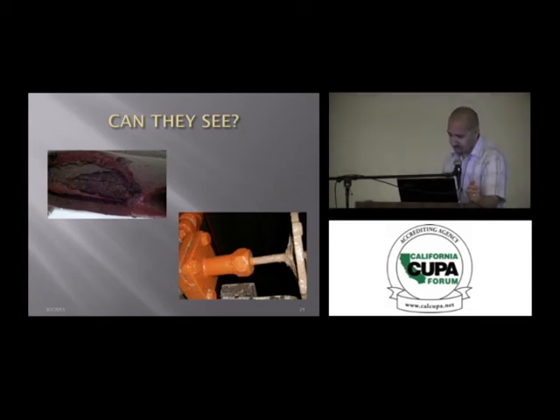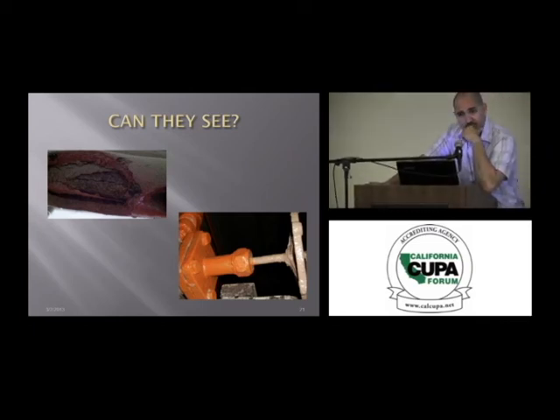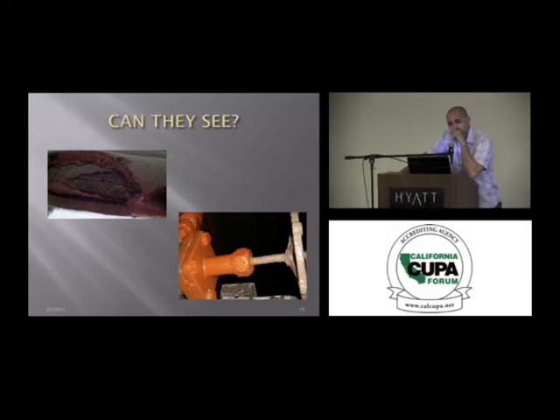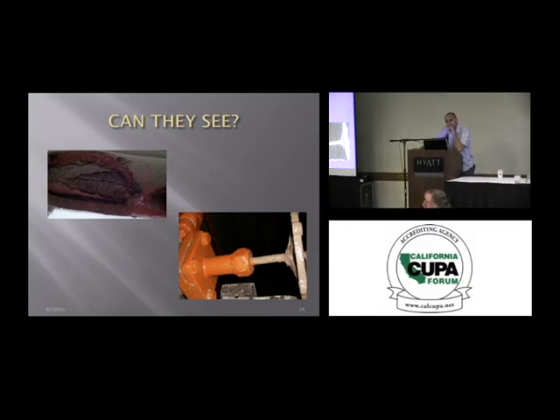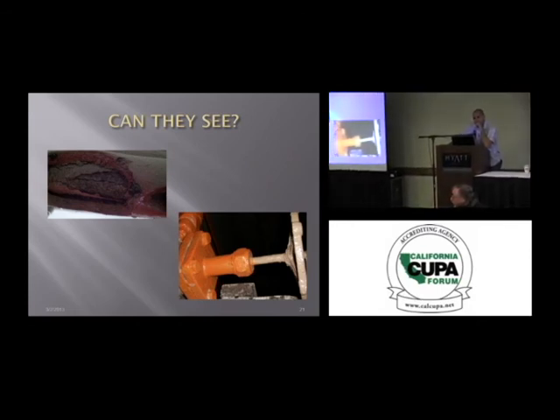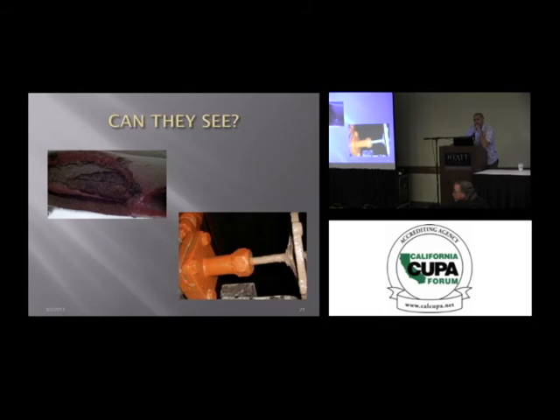There are times when we do it, when we have a system that shows signs where it has to be done, vessels, etc. But typically, they spend the money on replacing the pipe and insulation. Most of your facilities think their insulation is good for the life of the system. If you go to an insulation manufacturer, they will tell you the life expectancy of insulation is somewhere between 3 and 8 years. And that's if the vapor barrier is kept intact, people don't walk on it, and it was applied properly, which we didn't do at most sites.